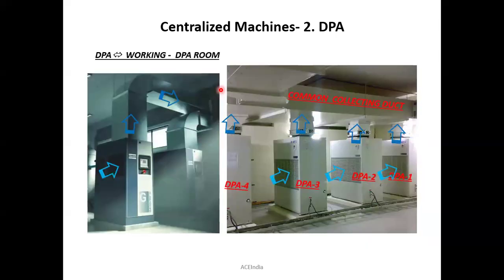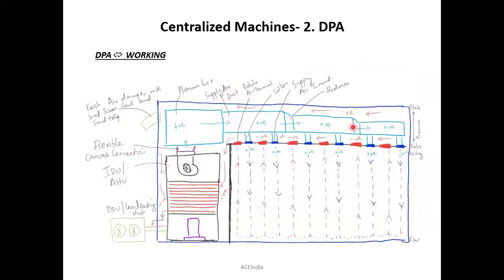Okay, so I will show the picture. You can see right here itself. Now, this is the common collecting duct, and these are the typical DPA connections, DPA 1, 2, 3, 4. And these whole connections are terminated right onto the common collecting duct right here itself. And from this collecting duct, you can take the ducting in either left, right, backside, or wherever you want. Okay, now, clear? So that is the purpose of a plenum box. Then the other connections are still the same. That means the duct connections will be there, air terminals will be there, especially supply air terminal and return air terminal.